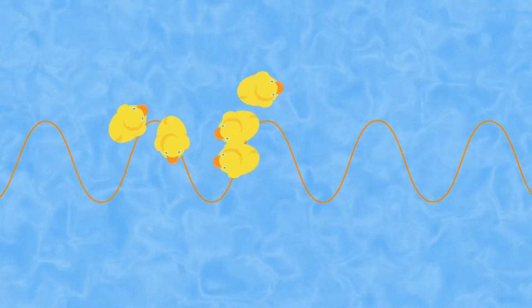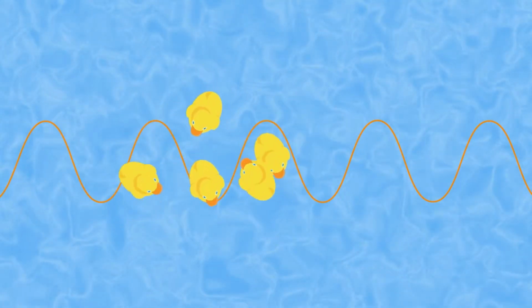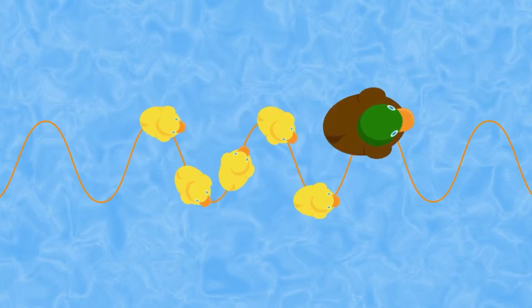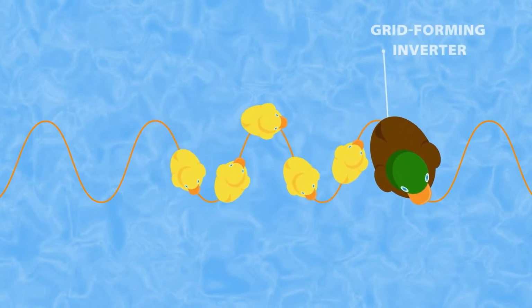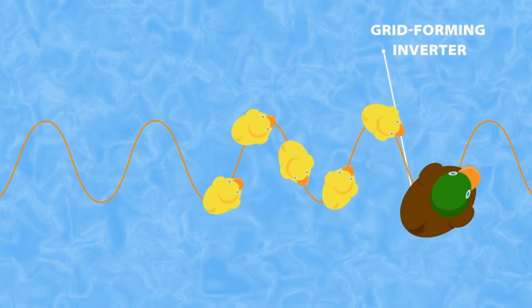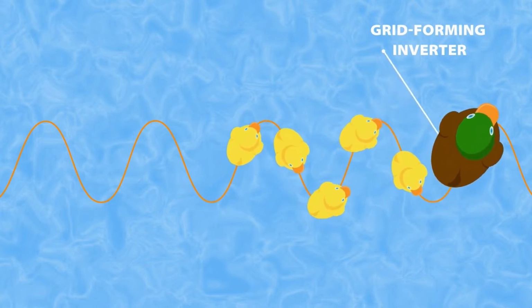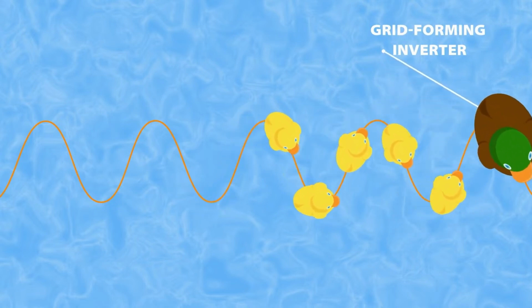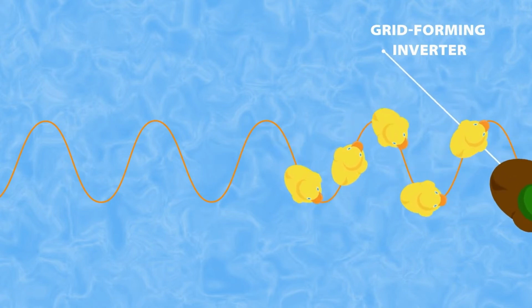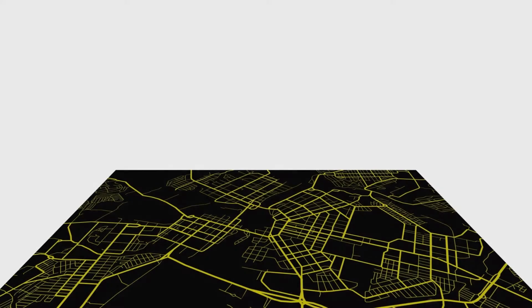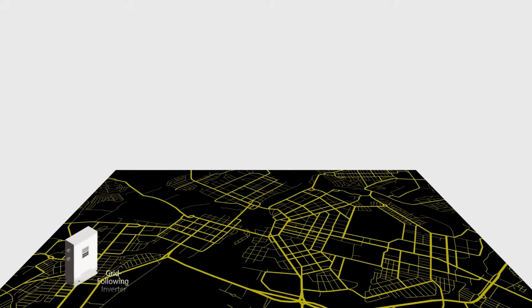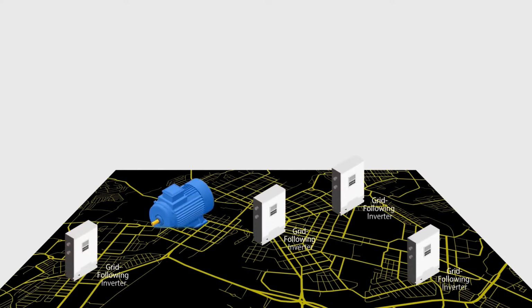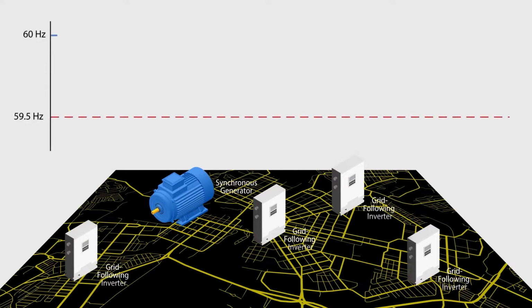To overcome this, power systems with large amounts of inverter-based resources require some of the inverters to form the grid. Grid-forming inverters generate electricity for other inverters to reference, providing a rapid response to maintain stability. For example, imagine a power system with mostly grid-following inverters and some synchronous generators which don't use inverters. Imagine that an inverter trips during a storm.